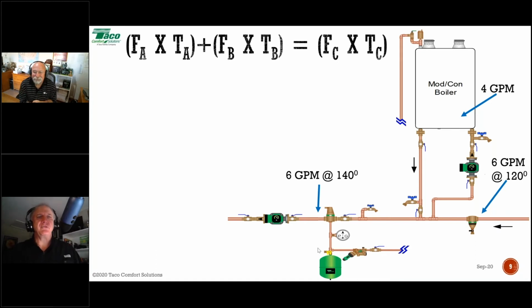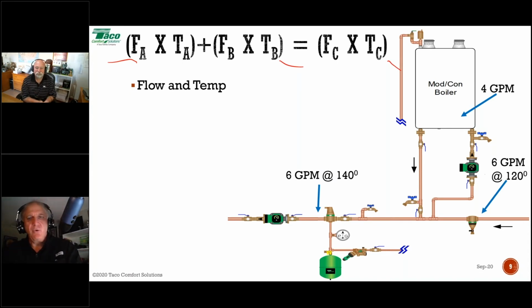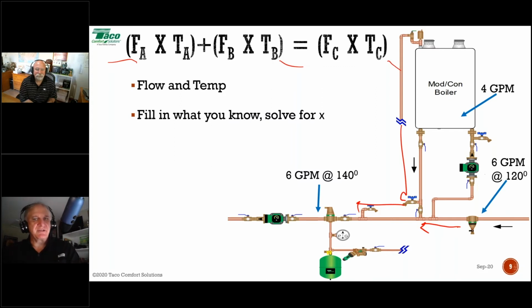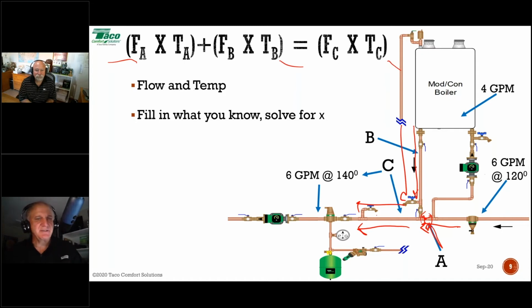All right, now all we've got to do is figure out A, B, and C. What's A, what's B, and what's C? Well, this is a mixing formula, right? We're mixing some of this with some of this to get all of this. So we just have to fill in what we know and then do 6th or 7th grade algebra and solve for X. So we have to figure out what we're talking about here. A is the flow and temperature in this common piping right here. That's A. We're mixing that. B is the flow and the temperature coming out of the boiler. And C is the resulting flow and temperature in my system. All right.